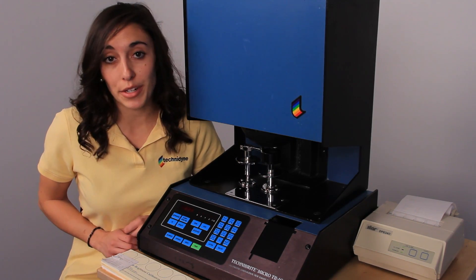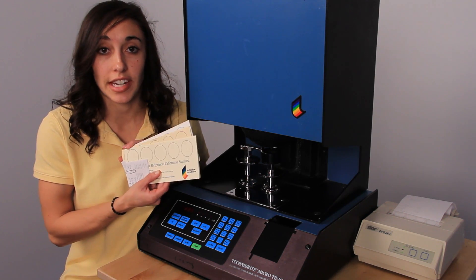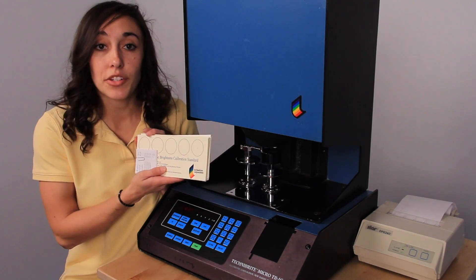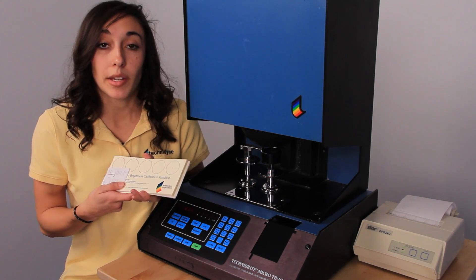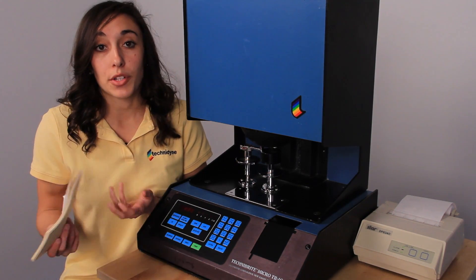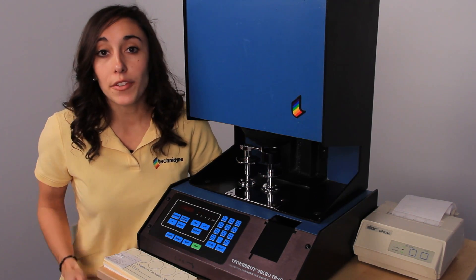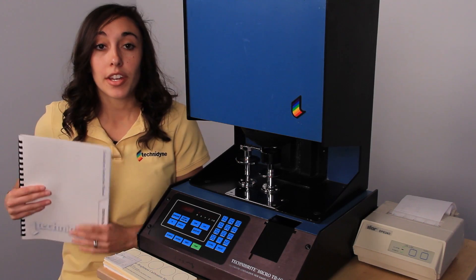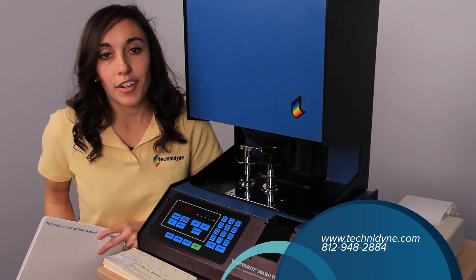Finally, in order to verify measurement linearity, you'll take the last four sets of verification standards and measure each of the five positions. You'll take the average of those five positions and compare it with the average on the printout. If those numbers are within plus or minus 0.3 of each other, then that's great. If they're not, or if you have any questions, you can refer to your Technidyne Operator's Manual, call Technidyne, or check out the website.